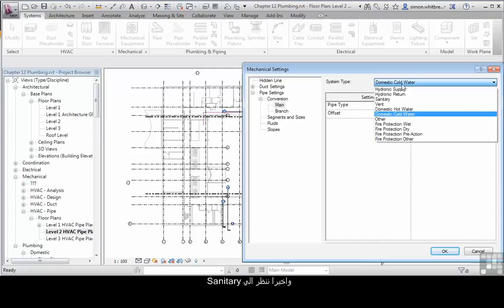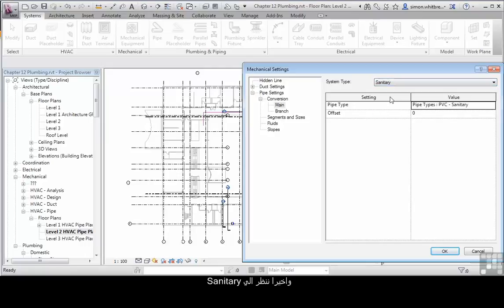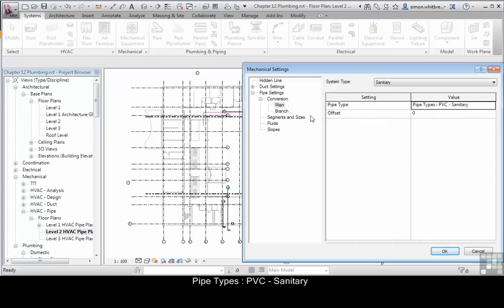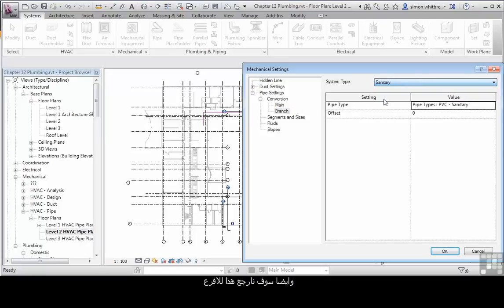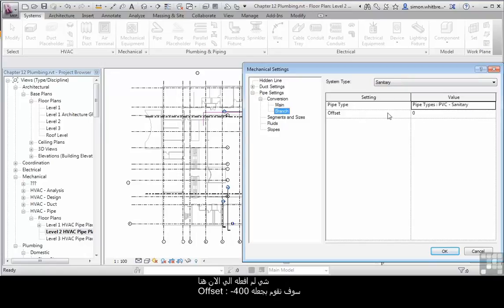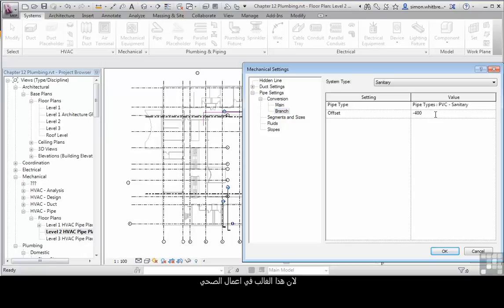Finally, we'll look at sanitary. For the main run, we've got pipe types PVC sanitary, and we'll also check that for the branch. One thing I haven't done though is the offset for the current level. We can create a default offset of minus 400, as that's where most of the pipe work is going to be, below the actual grade.